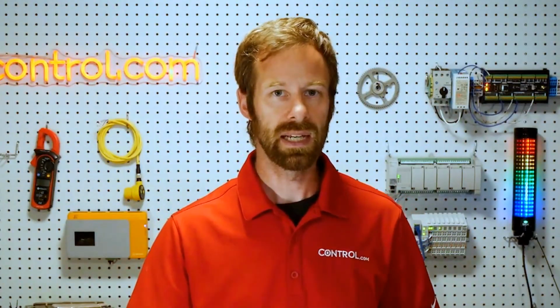Not very many individual sensor devices have Modbus built into them, which means that often what we're going to be doing is sending Modbus communication between the PLC and a remote I/O. That remote I/O is going to be connected to the discrete sensors and the analog sensors. So it accomplishes the task of data transmission, but not by connecting to the sensor directly. That's what I mean when I say we've reached a third level of bidirectional communication.